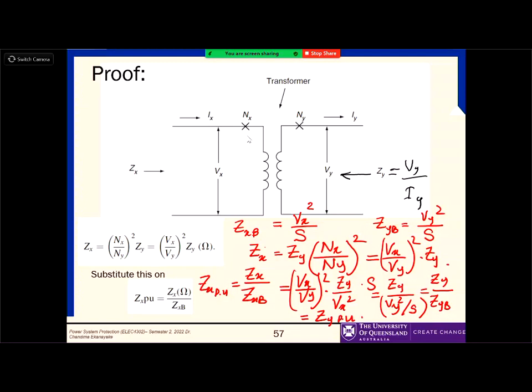Now can you see that Zx per unit is equal to Zy per unit? Why is it equal? Because when you define the base quantities, you used the transformer voltages equal to the turns ratios. That is the point there. If you didn't use it, then Nx divided by Ny would not equal Vx divided by Vy. So always, therefore, the turns ratio has to be equal to the voltage ratio. That comes only when you refer it to the corresponding correct voltages.